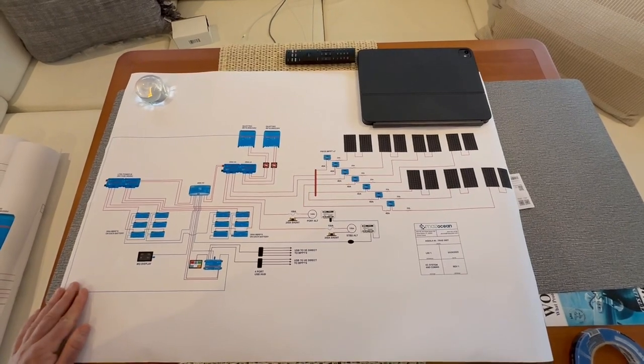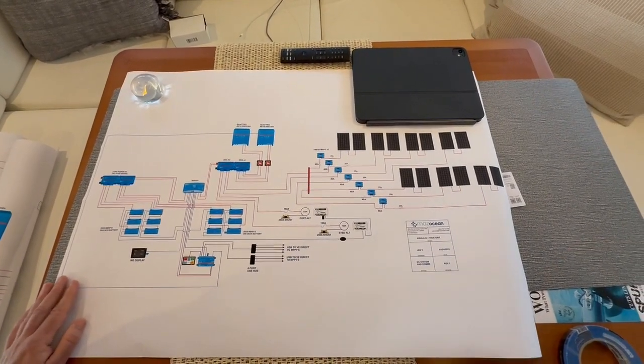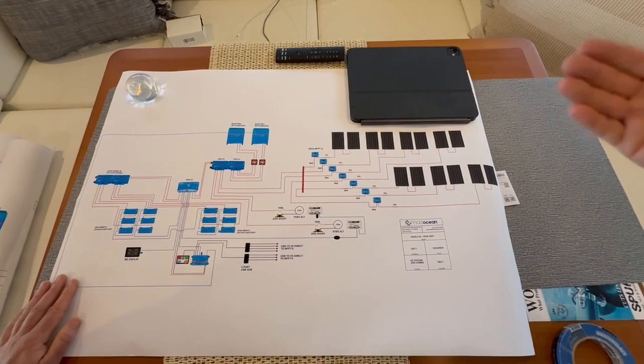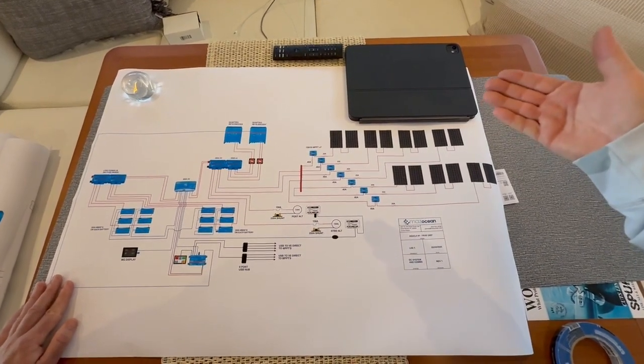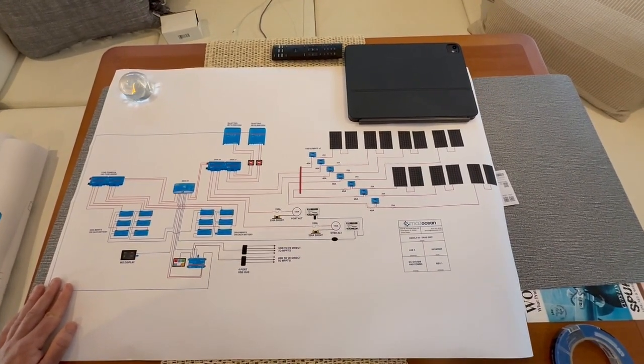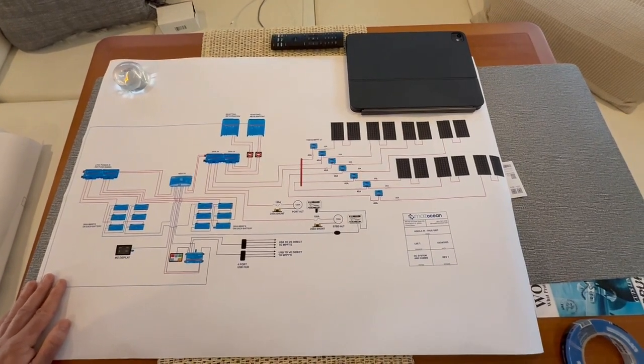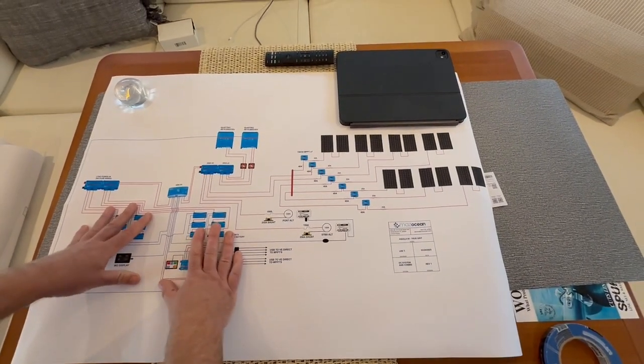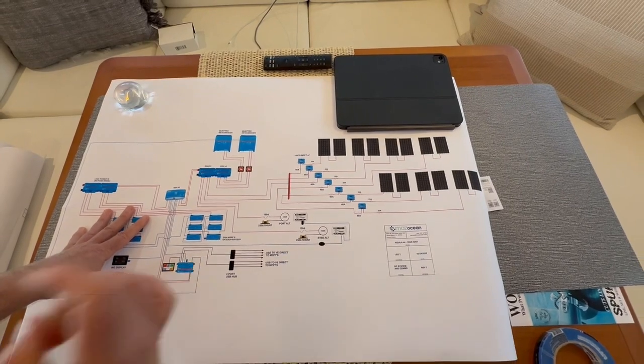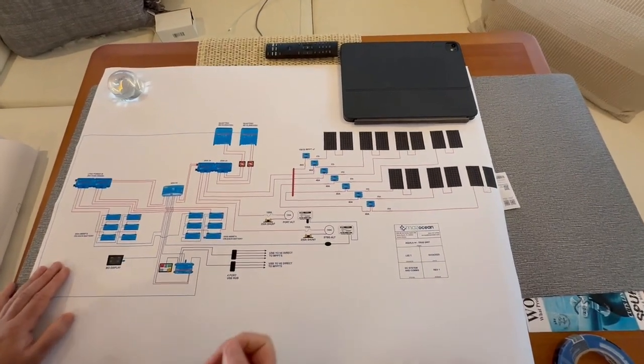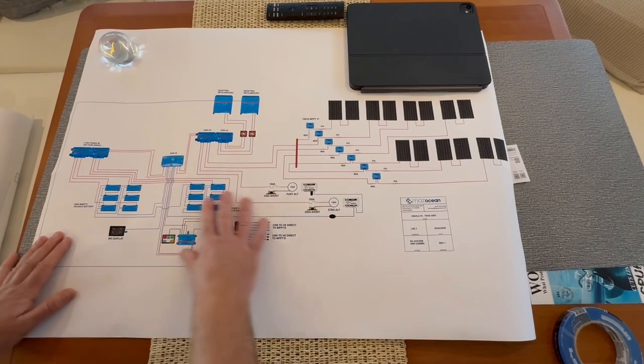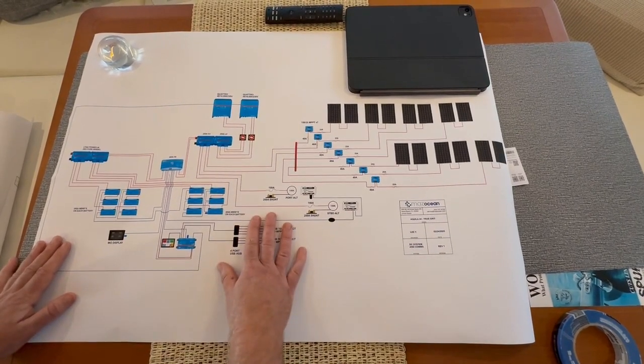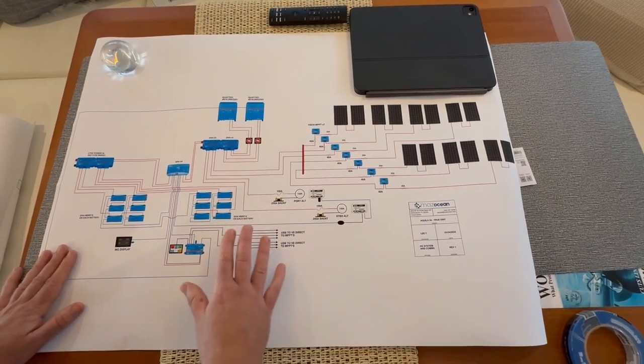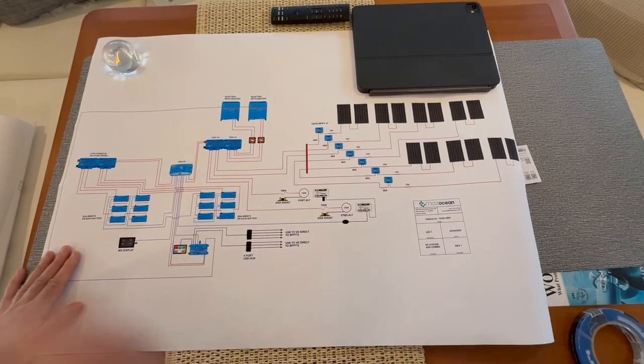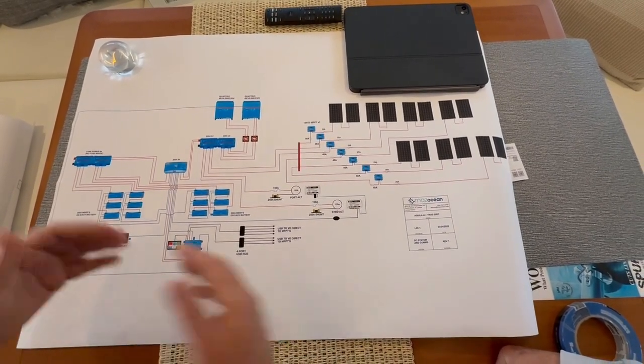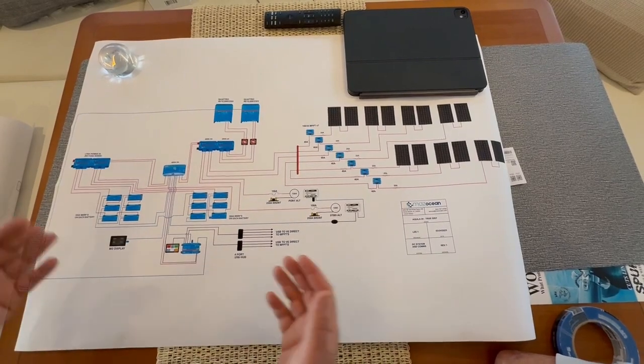Am I correct in saying that's voltage drop you want to be very careful with? Correct. That's the practical application—if you're going to do this yourself, you really need that knowledge base and understanding. Voltage drop based on wire length is important, but voltage drop based on wire size, the gauge and how thick the wire is, is also a massive factor when doing DC side direct current wiring. On the alternating current side, wire gauge is important, but wire length is irrelevant up to a certain point.